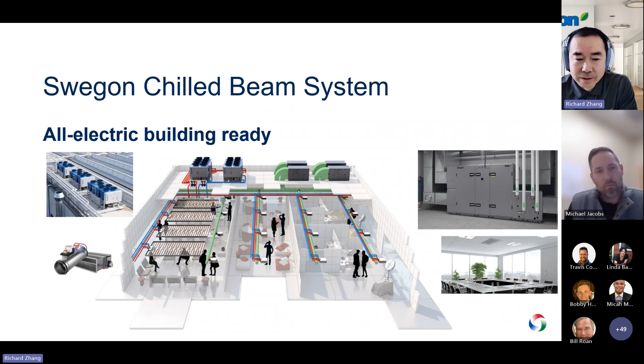Going back to the chilled beam again - because there are no moving parts, the maintenance is pretty much minimal. On the other hand, that can be bad news for a noise control guy - there's no noise, no draft, less stratification, so it's much more comfortable for the occupant.